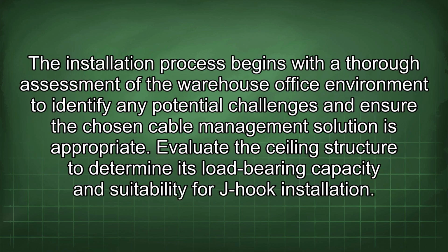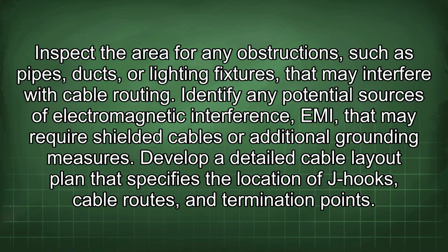The installation process begins with a thorough assessment of the warehouse office environment to identify any potential challenges and ensure the chosen cable management solution is appropriate. Evaluate the ceiling structure to determine its load-bearing capacity and suitability for J-hook installation. Inspect the area for any obstructions, such as pipes, ducts, or lighting fixtures, that may interfere with cable routing. Identify any potential sources of electromagnetic interference (EMI) that may require shielded cables or additional grounding measures.